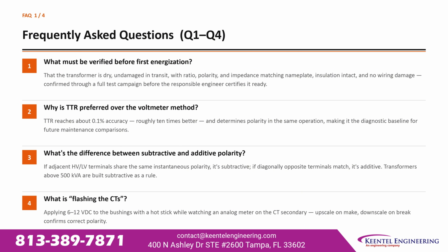What's the difference between subtractive and additive polarity? If adjacent HV and LV terminals share the same instantaneous polarity, it's subtractive. If diagonally opposite terminals match, it's additive. Transformers above 500 kilovolt amperes are built subtractive as a rule.